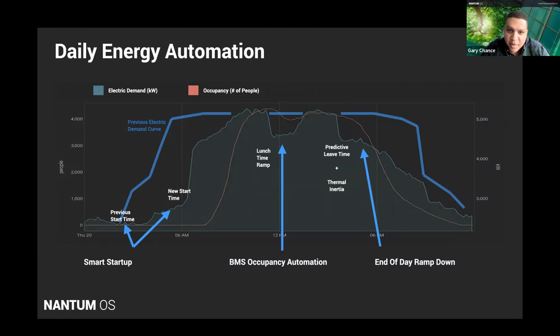What you see here, and we'll dive into later in the actual demo, is that throughout the day at lunchtime as people leave, we reduce the green part of the chart, the electric demand in kilowatts, based off real-time occupancy. And as people return, we ramp back up the building, always guaranteeing comfort.